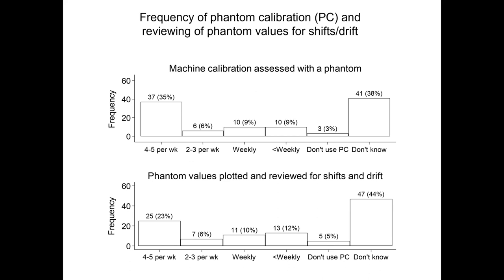Phantom values were plotted and reviewed for shifts and drift 4 to 5 times or more each week in only 23% of the centers, and you can see the unknown responses there being greater than 40% again. So there's work to be done on calibration using phantoms and drift in measurements over time.